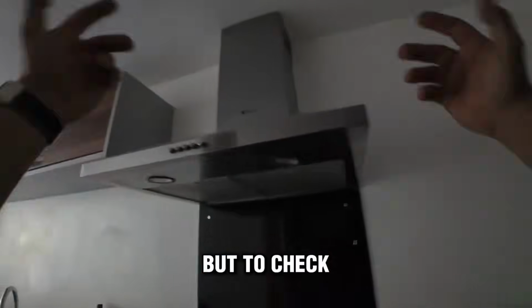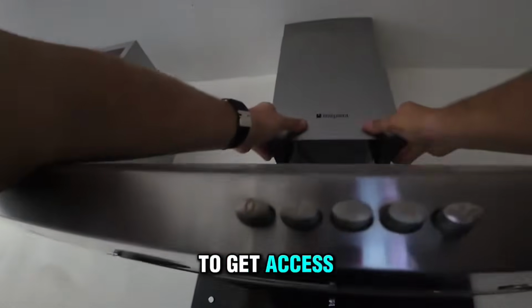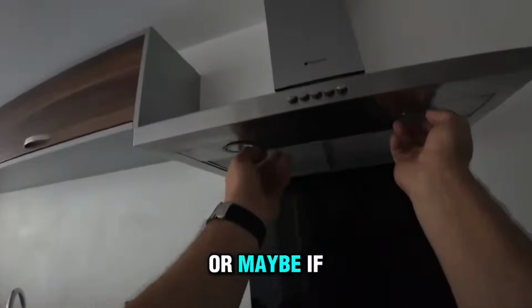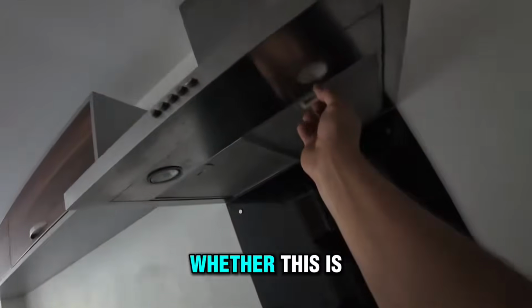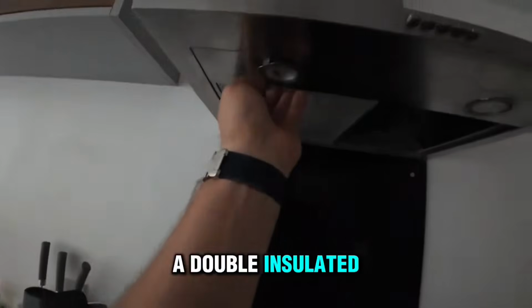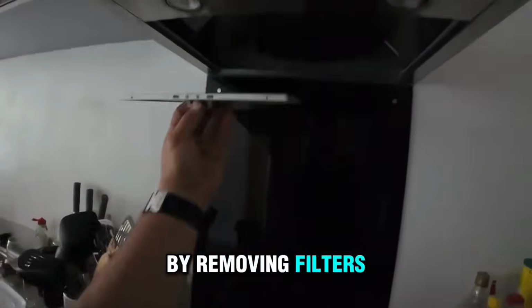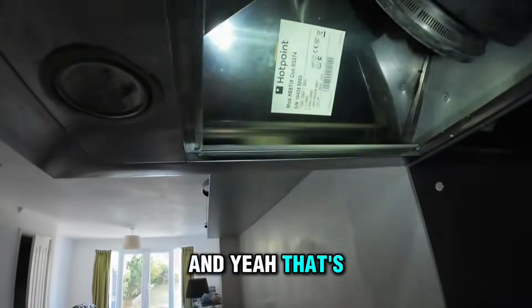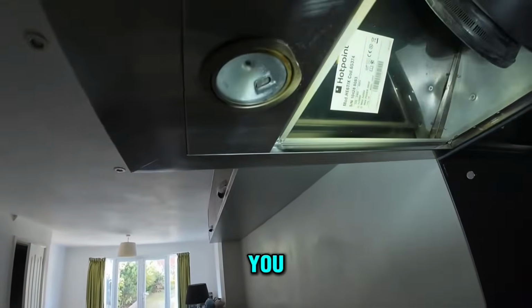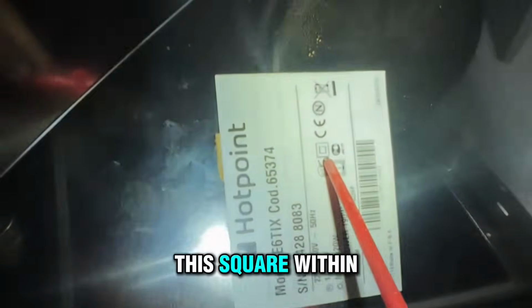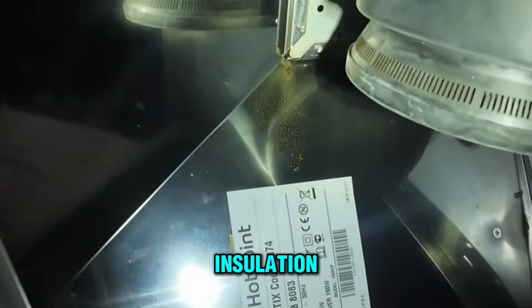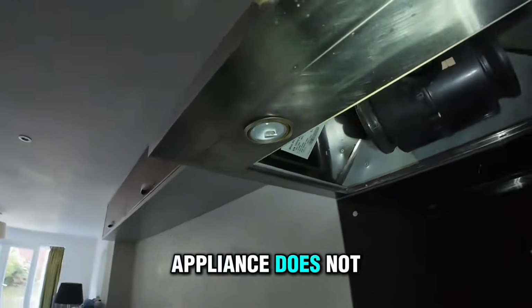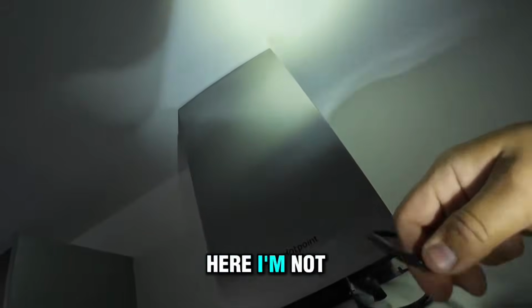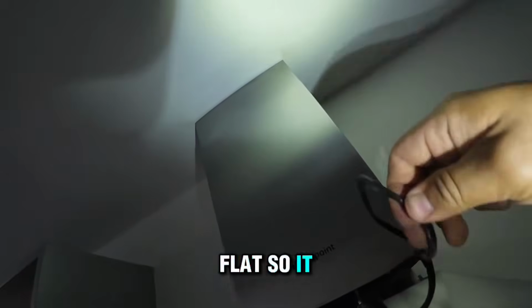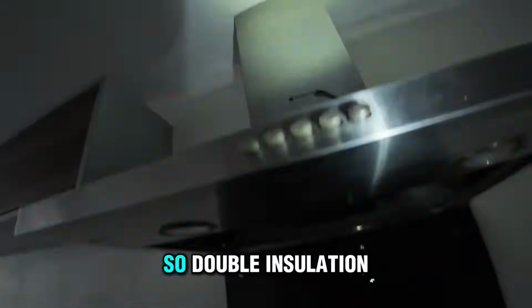But to check that, we need to get access to the connection behind, or maybe find a label from below, whether this is a double insulated appliance or not, by removing filters. And yeah, that's what we're looking for. Let me point it out to you. We're looking for this square within a square, so that's double insulation. That means the appliance does not rely on the means of earthing. Even the cable here, I'm not sure if you can see it, is flat, so it doesn't even have the earth inside. So double insulation.